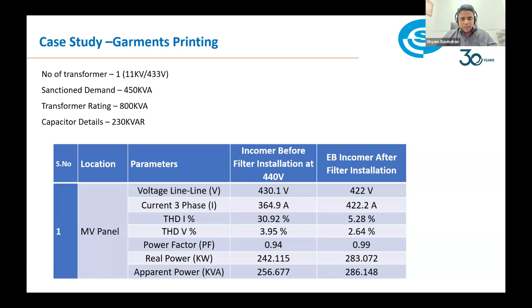So here the customer went for a 100 ampere active harmonic filter with 230 kVAR, the complete 230 kVAR on detuned filters. I've shown it on THD intentionally because the customer worked it out on THD. It's also an interesting question, but you mentioned THD is on the fundamental current, not at the maximum load current. True, because when you address this problem at the fundamental current, the difference between the fundamental current and the load current could be significantly higher.